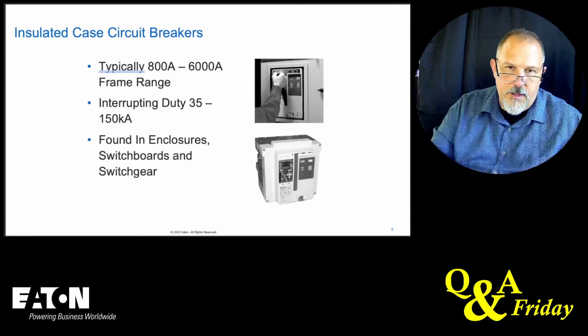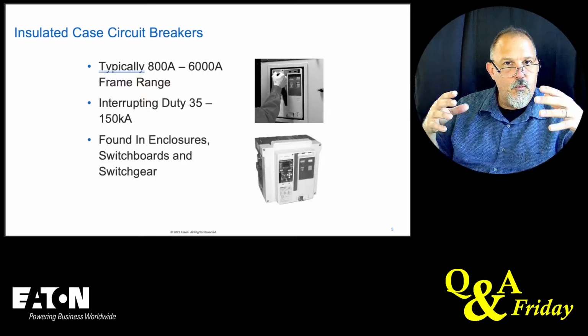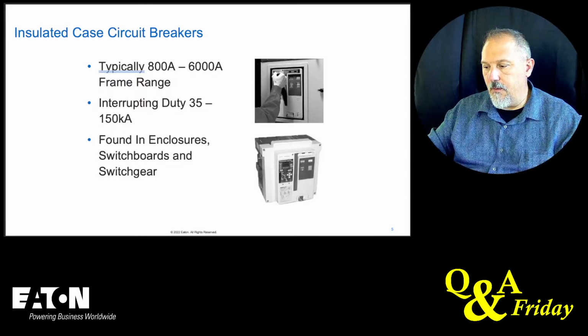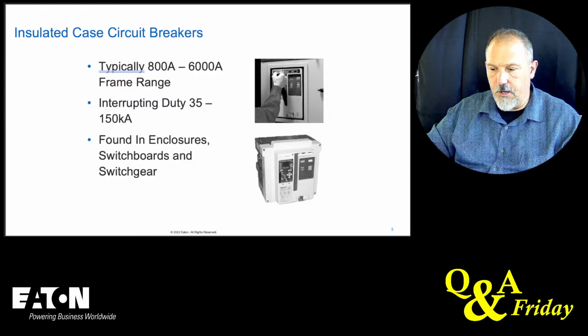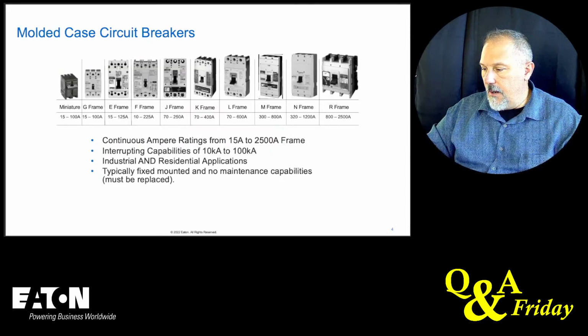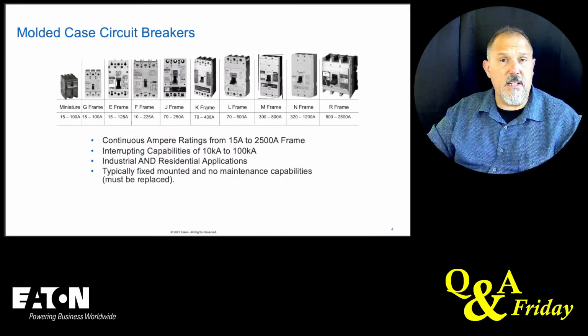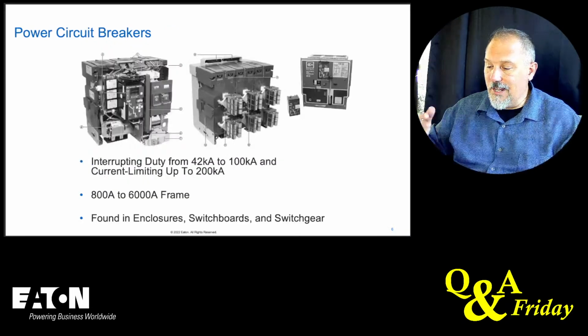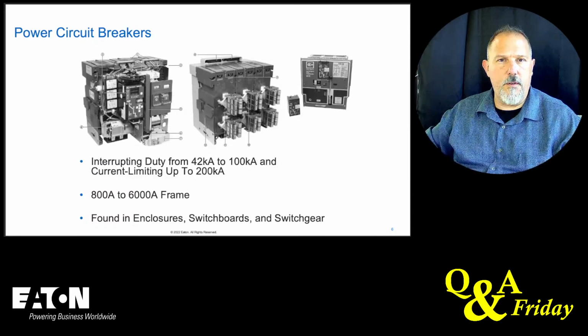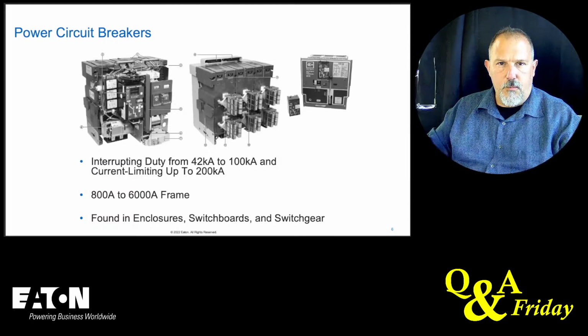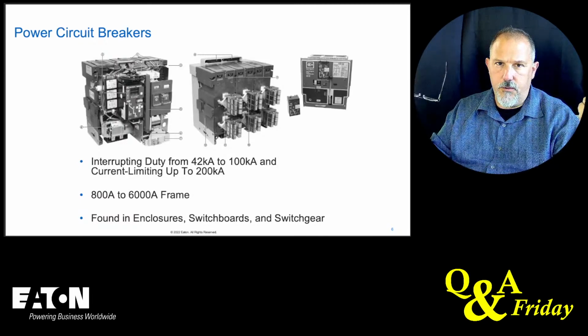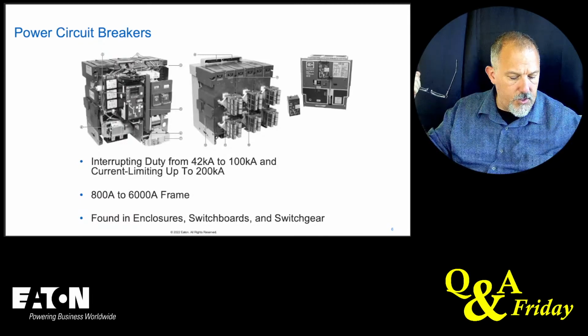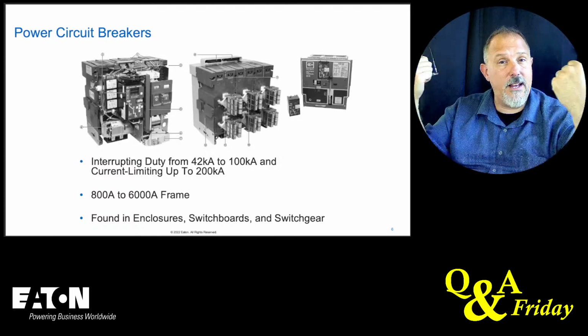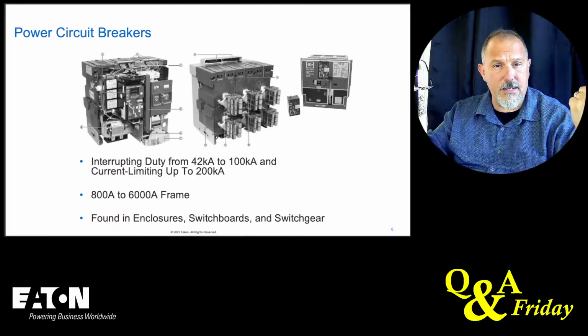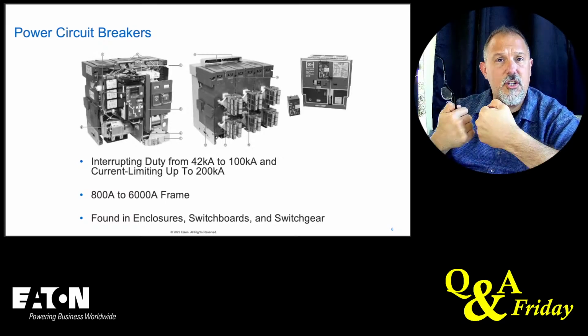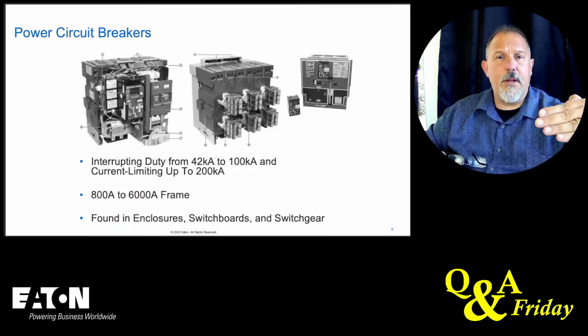So if you've been to any one of my programs, you should recall the reason I, like, say an 800 amp insulated case circuit breaker versus buying an 800 amp molded case circuit breaker, which is much smaller, probably a lot less expensive in many ways, versus an 800 amp power circuit breaker. Why would I pick one over the other? The challenge for a circuit breaker is not necessarily opening those contacts, because as the person who asked this question stated, we leverage the magnetic forces to open those contacts. The challenge is holding those contacts closed for a longer period of time.